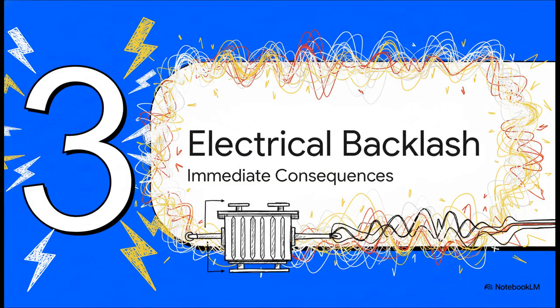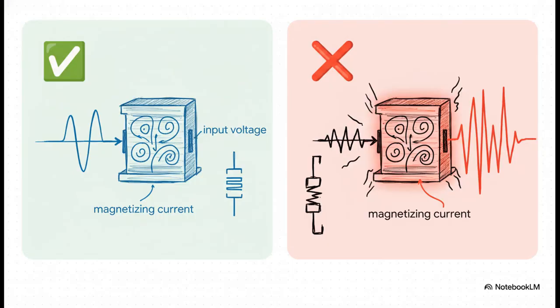So once that line is crossed, the backlash is immediate, and it is severe. In an instant, the transformer's electrical personality completely changes, and it stops behaving like a transformer at all. Let's have a look at how this backlash actually builds up. And this just shows you the stark contrast. Normally, the core provides high inductance, which acts like a big, strong dam, holding back the current, keeping it small and controlled. But when you hit saturation, the core's ability to support that magnetic field just evaporates. The inductance collapses, the dam breaks, and the magnetizing current, which was a tiny trickle before, suddenly skyrockets into a flood, completely distorting that clean, beautiful sine wave we need for our power.